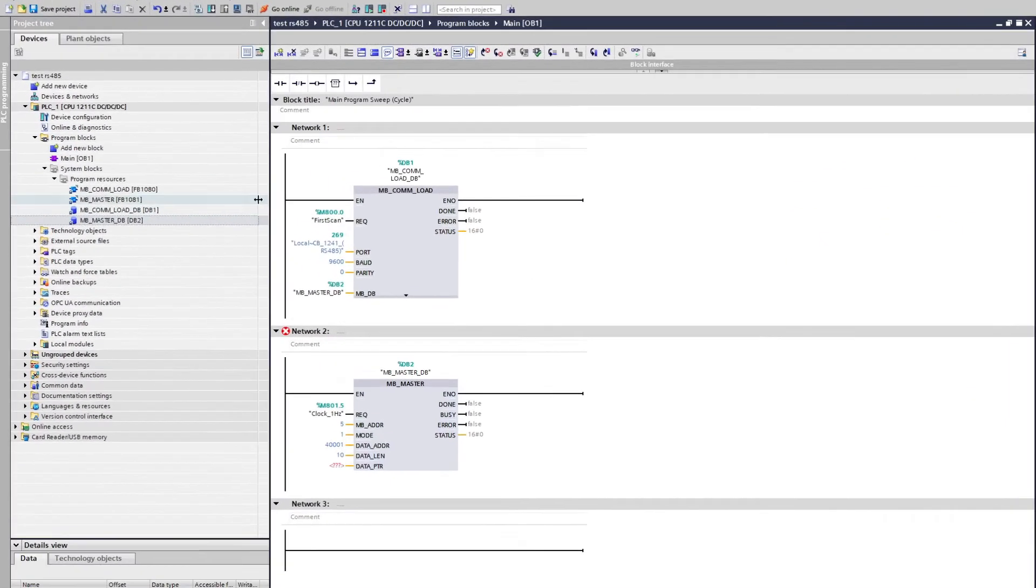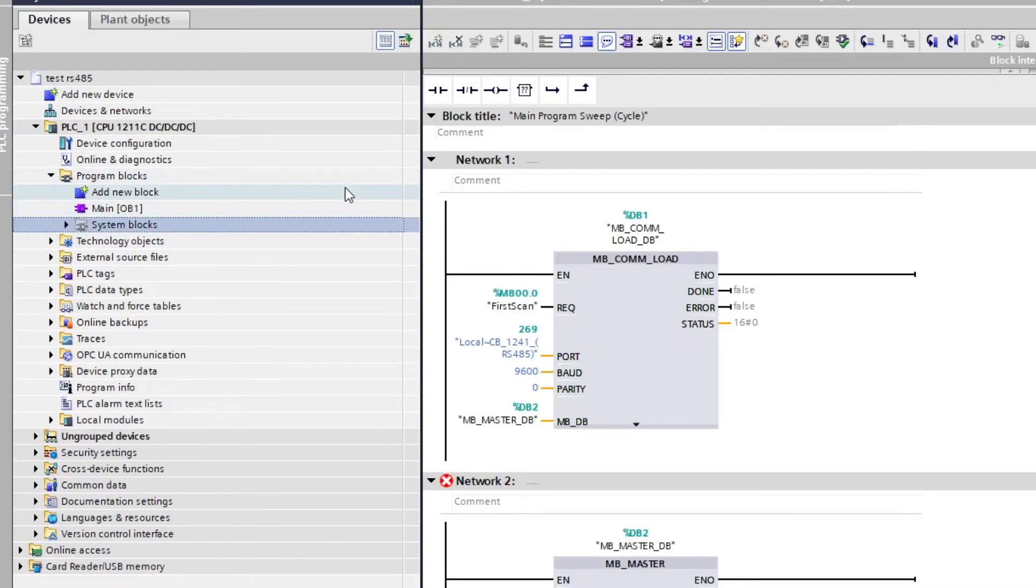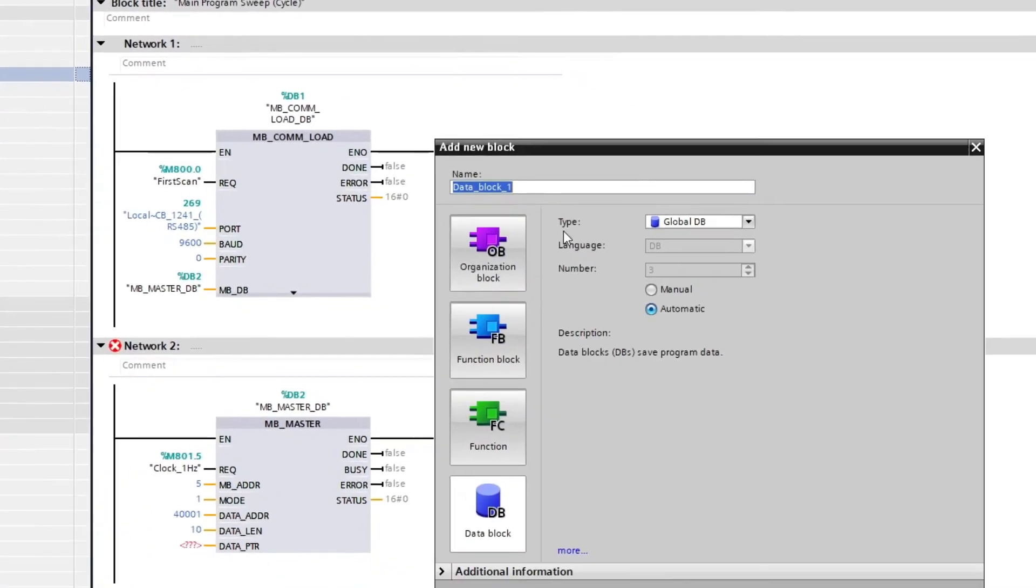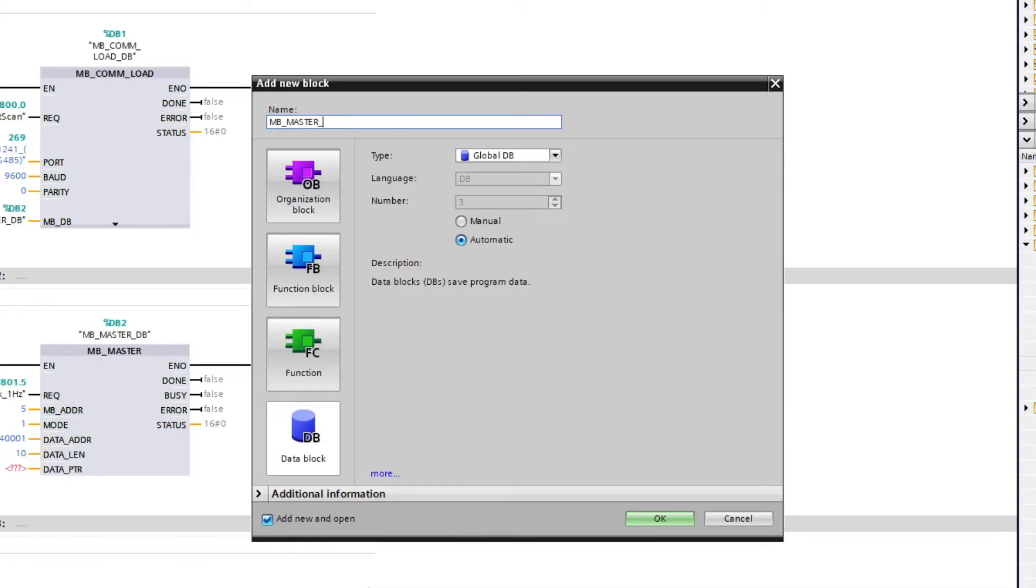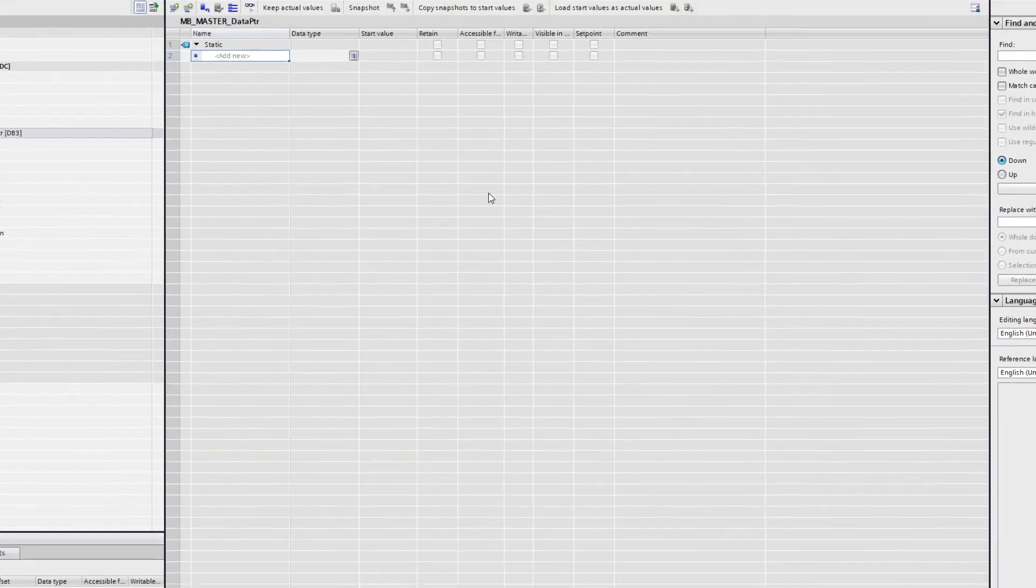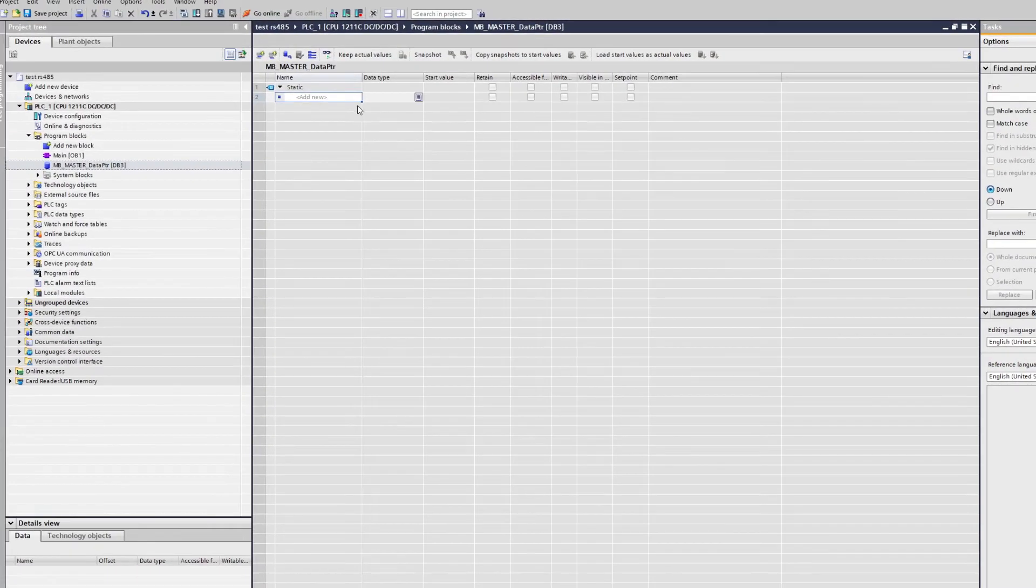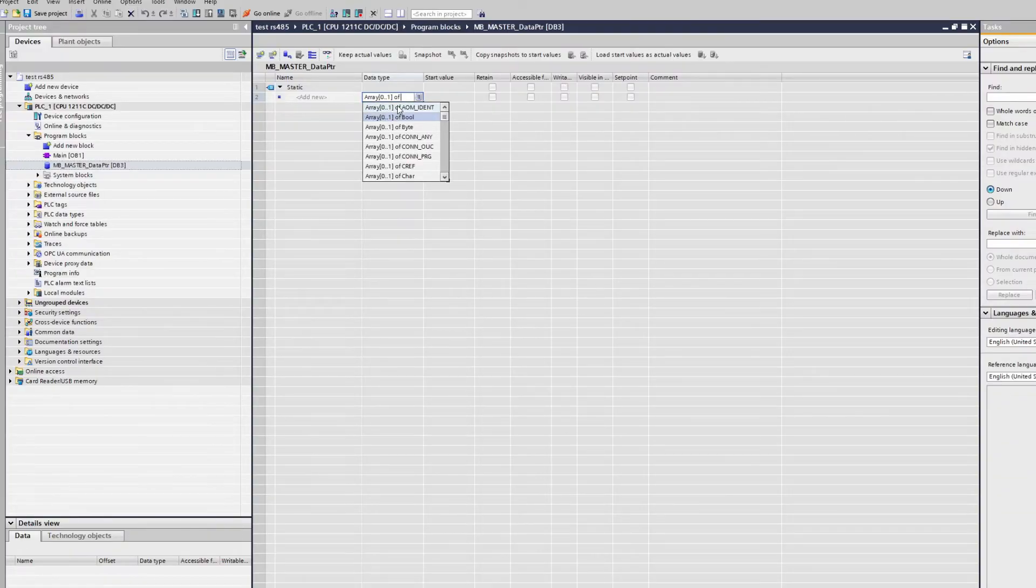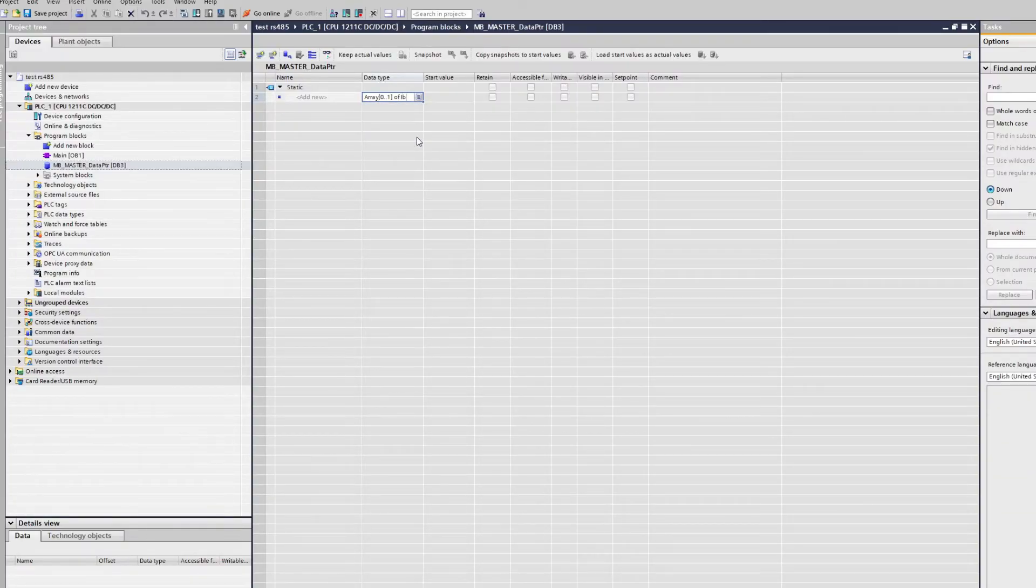For the data pointer input I want to make a new global data block. This is where we add the PLC's tags we want to write. I will make an array of integers with the limit of 0 to 9, which will give me 10 integer tags that I can write.